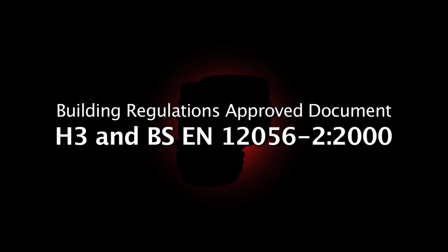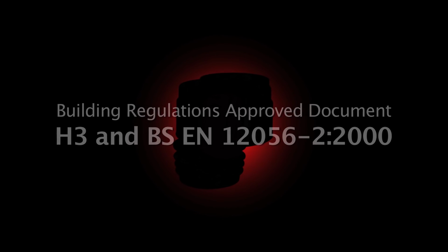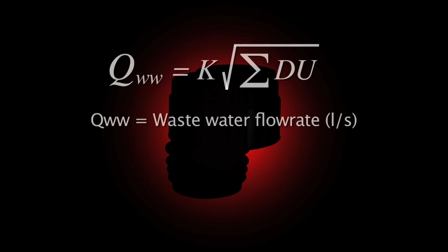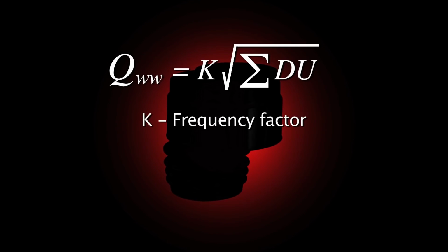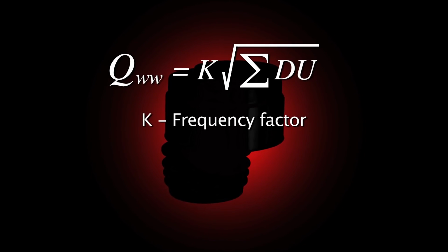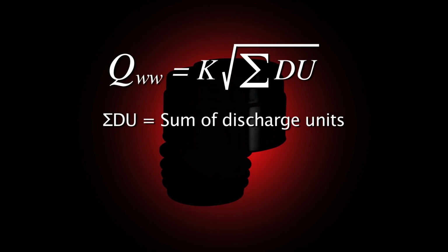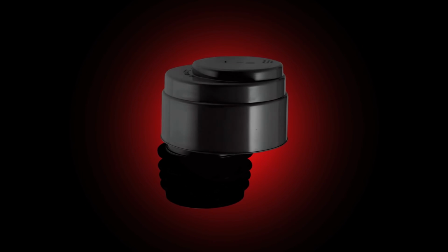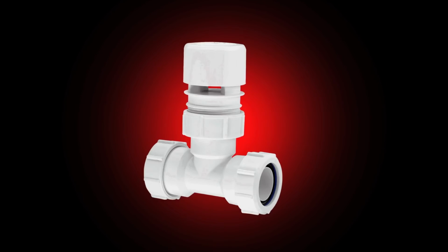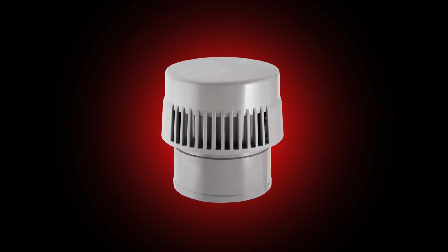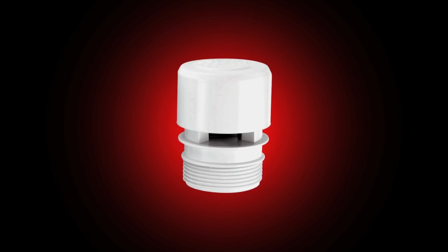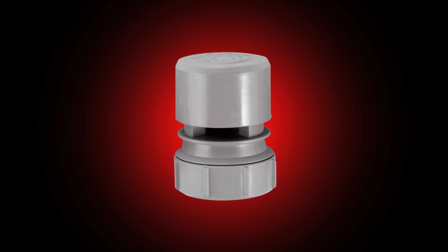The use of AAVs is approved under Building Regulations Approved Document H3 and BS EN 12056, though only AAVs manufactured to BS EN 12380 are suitable for use in sanitary pipework systems. The airflow rate of any AAV needs to be taken into consideration when the system is designed or being modified. It is important when dealing with multi-storey buildings that the AAVs are sized correctly and in accordance with BS EN 12056, which states that the valve has to be 8 times the peak airflow rate of the soil stack. Where an AAV-equipped drain serves more than 4 stories, there are specific rules about how the drain should be vented.